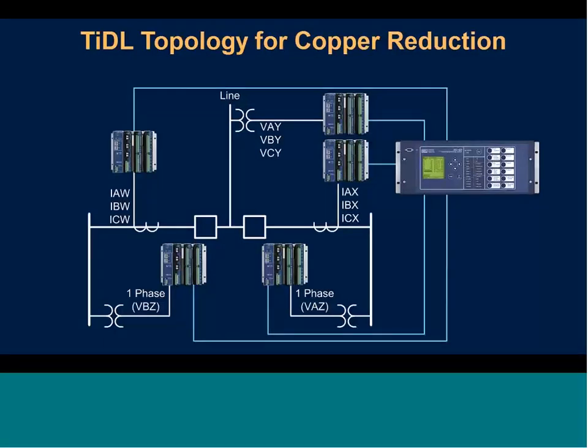So the topologies that I talked about earlier, here's a couple of examples to show the points we were discussing, copper reduction versus device cost. This would be, for instance, a topology for copper reduction. This is one example from the 421. This is a breaker-and-a-half scheme, and we have 5 Axion devices. So we have to use a lot of Axions, but the trade-off is I can put them right next to the device that I'm actually measuring. If this was a physically large substation, and all these CTs and PTs are located far apart, I can instead just run one fiber connection instead of having to run all my copper to a centralized location. And then all of those fibers go back to the relay and connect into the different ports on the relay.